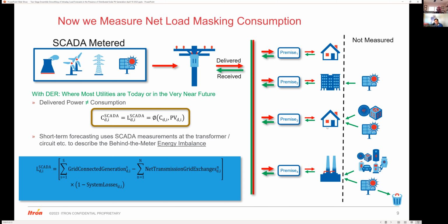To come up with these dynamic operating limits, which are at the 5-minute level for a rolling 48 hours, we're literally forecasting the net load at each premise. If there's 1 million premises, we're producing 1 million forecasts every 5 minutes. Those forecasts also leverage forecasts of what the rooftop solar is doing.